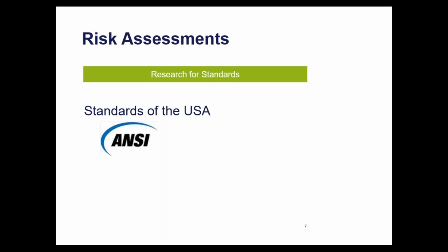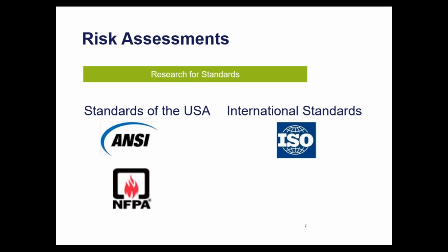standards that might be applicable, like NFPA 79, which is the electrical standard for industrial machinery. Under ISO, we have ISO 12100 from 2010, also called safety of machinery. Both the ANSI and ISO standards talk about risk assessment and risk reduction. They provide guidance on those. Then we have the IEC in Europe that also talks about risk assessment. They mainly make reference to ISO standards.